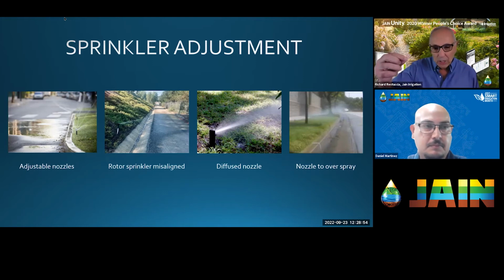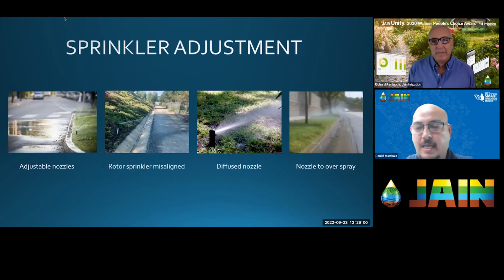There's a screw on top of the head that screws down into the nozzle. Is that what's happening? Correct. That screw is actually designed to retain the different nozzles you can put into that sprinkler to adjust the distance. You normally adjust distance by changing to a different nozzle with a larger orifice.